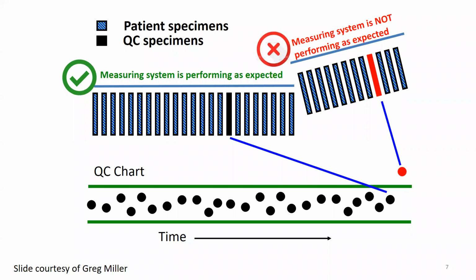However, if QC values exceed the acceptance limits, representing an out-of-control event, this may indicate an out-of-control condition where the measurement procedure is not performing as expected. Out-of-control conditions are usually identified by a shift or drift of QC values away from the target mean or an increase in assay imprecision. A QC drift, shift, or increase in imprecision identified by an out-of-control alert means that something happened to the measuring system that could be causing us to report erroneous patient results.